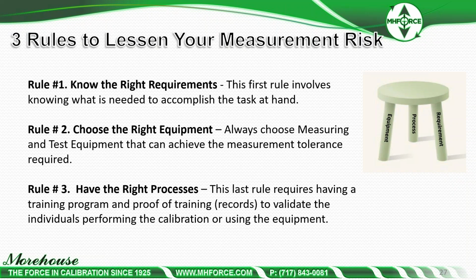The first rule involves knowing what is needed to accomplish the task at hand. Choose the right equipment. Always choose measuring and test equipment that can achieve the measurement tolerance required. Have the right process. The last rule requires having a training program and proof of training to validate the individuals performing the calibration or using the equipment.